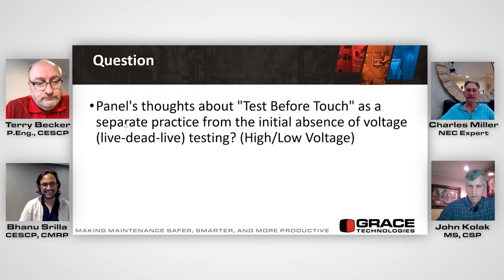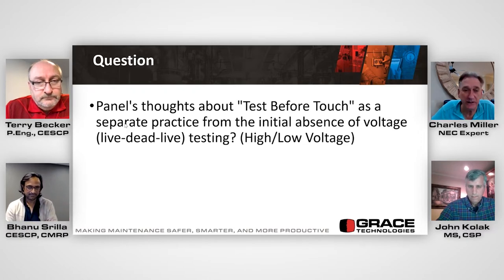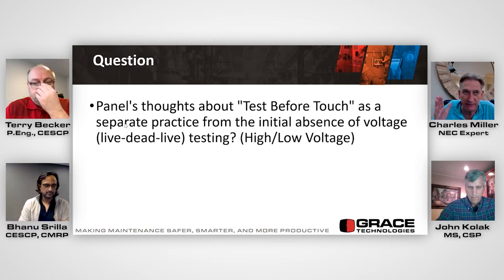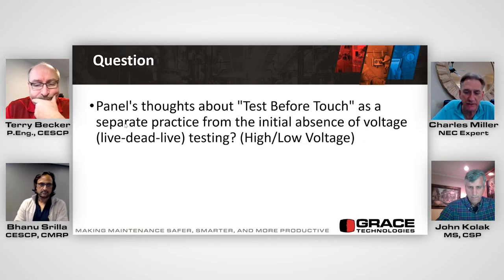All right, in 70E, this is a great question. 70E tells us that to establish and verify equipment is in an electrically safe work condition, there are eight steps. Typically, step eight is going to be over 1,000 volts.